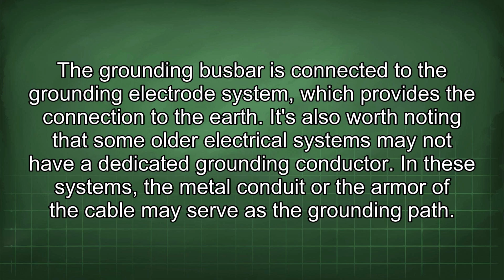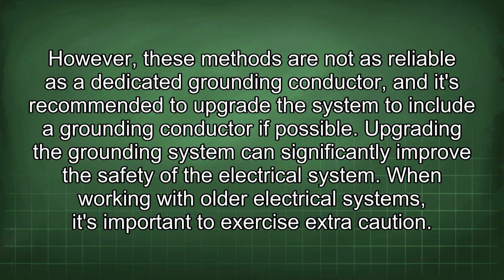It's also worth noting that some older electrical systems may not have a dedicated grounding conductor. In these systems, the metal conduit or the armor of the cable may serve as the grounding path. However, these methods are not as reliable as a dedicated grounding conductor, and it's recommended to upgrade the system to include a grounding conductor if possible. Upgrading the grounding system can significantly improve the safety of the electrical system.